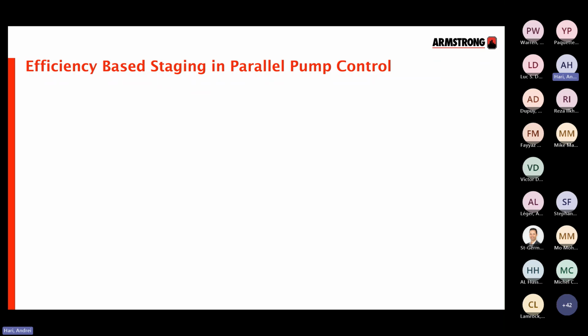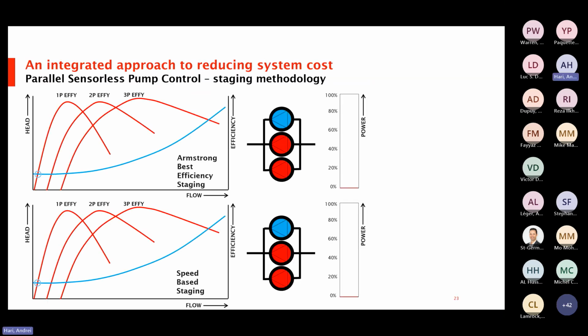So, efficiency-based staging. One of the other functionalities now is that instead of the traditional staging of pumps based on speed, what we're able to incorporate is staging based on the pump's hydraulic efficiency. And what that means is that in traditional systems with BMS controls, first of all, on a speed-based system, we know that a pump can provide up to 90 to 100% of its design flow.